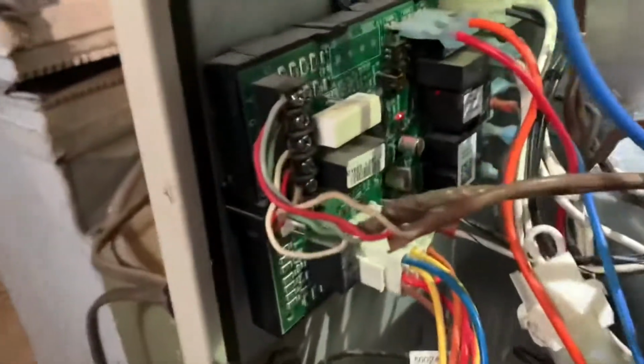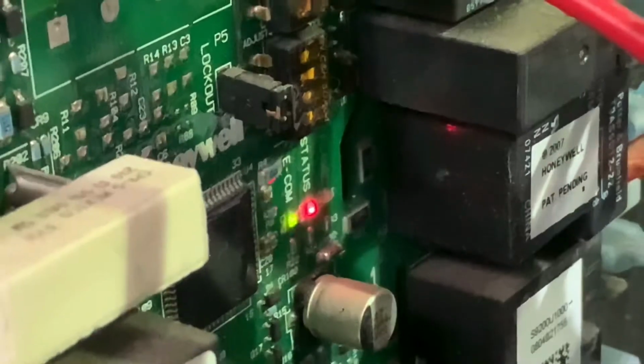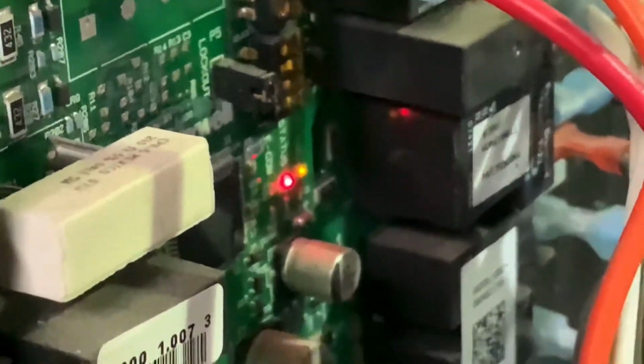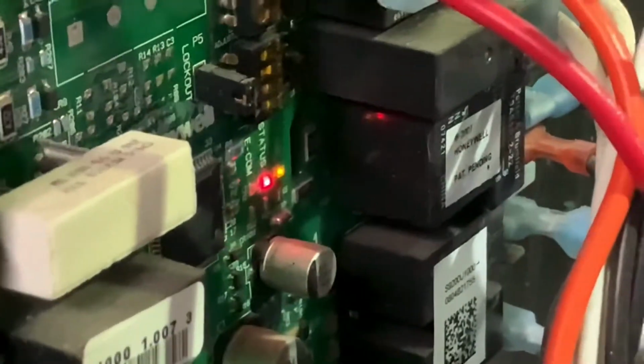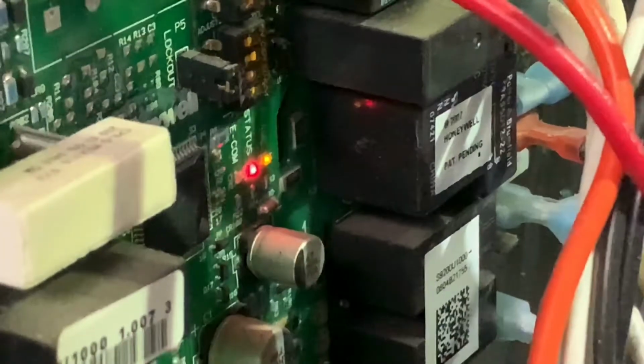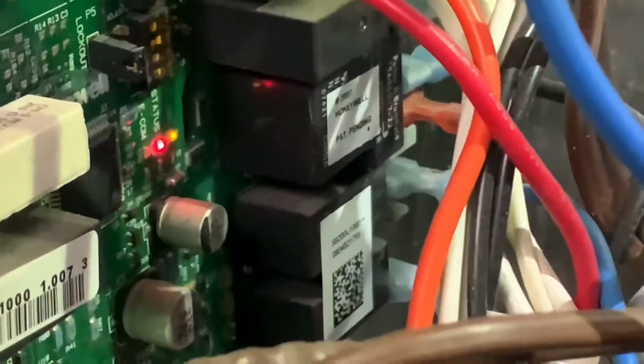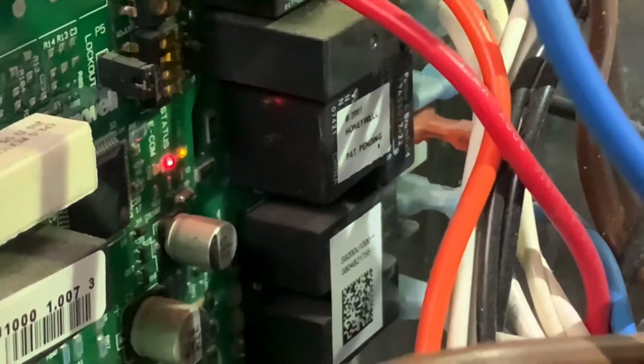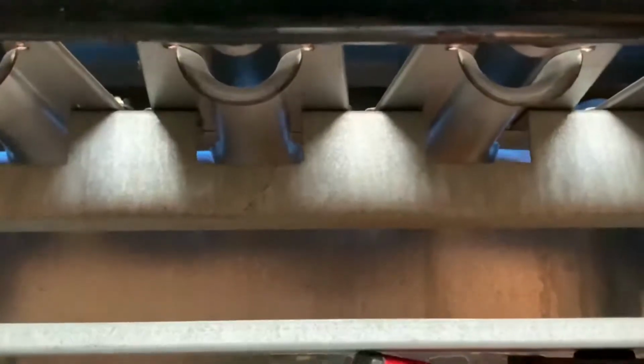Okay, so on this service call here, I was getting a fault code. See the red light in the board? The red light is the status, and it gives you your fault codes as well. So I was getting 4 flashes, and 4 flashes mean flame loss, right? But also take note, the yellow or the amber light or LED on the board, that's your flame signal. Right, so it comes from your flame sensor.